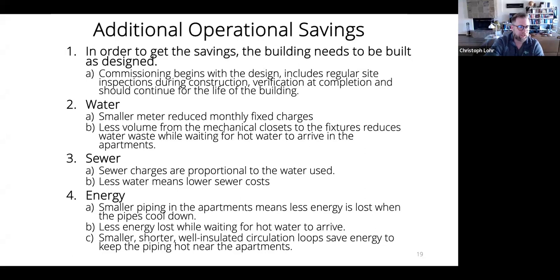The other part is energy. There is a water-energy nexus. We've talked about this for quite a bit over the last 10, 20 years as an industry. When you have smaller piping, the surface area of that pipe decreases, which means in hot water systems you have less surface area to dissipate heat to the space, which saves energy. It also helps keep the water hot at lower flow rates to get to the various fixtures that it serves.